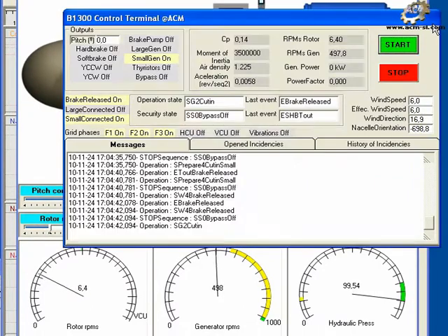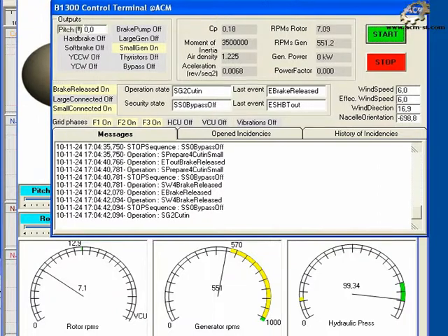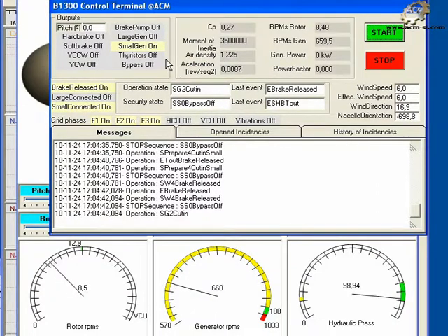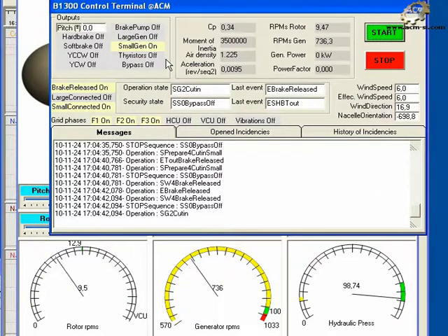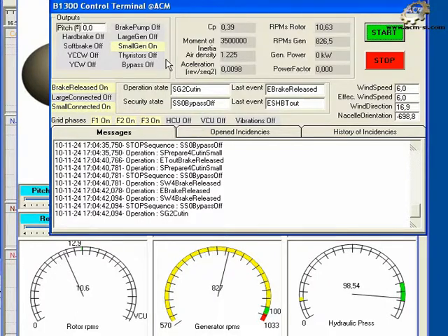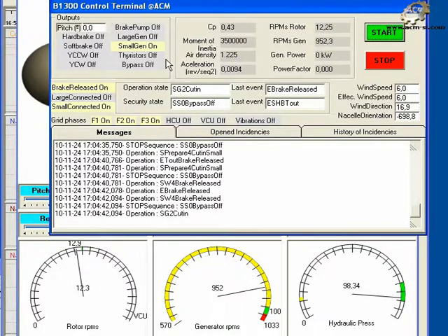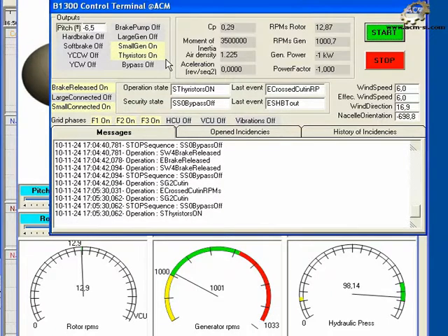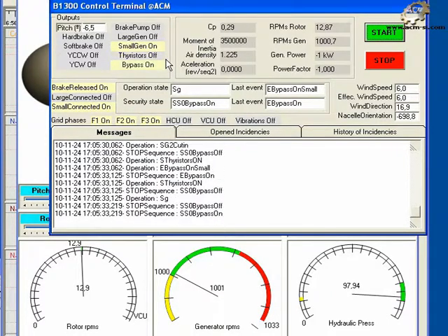Layer the control terminal synoptic on top of the nacelle synoptic so they are both visible. Watch as the RPMs approach small connection synchronous speed, or 1,000 RPMs. A message is received that the thyristors are on for a few seconds. And finally, the bypass is on.